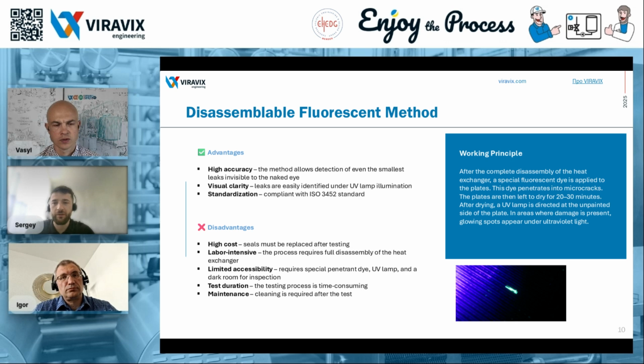Yes, this method is mostly used after it has already been confirmed that the heat exchanger has a leak, specifically an internal leak, and it's necessary to determine which plate is causing it. That's why the unit needs to be disassembled, and this method applied.